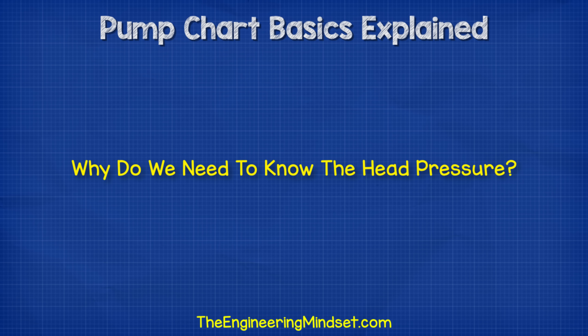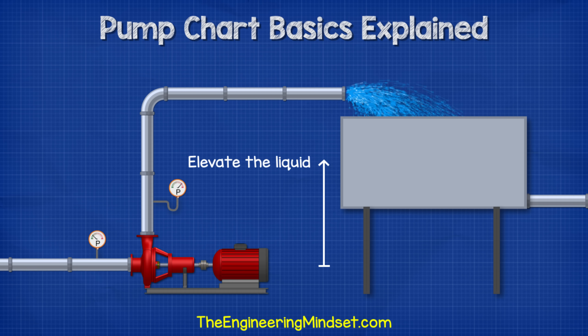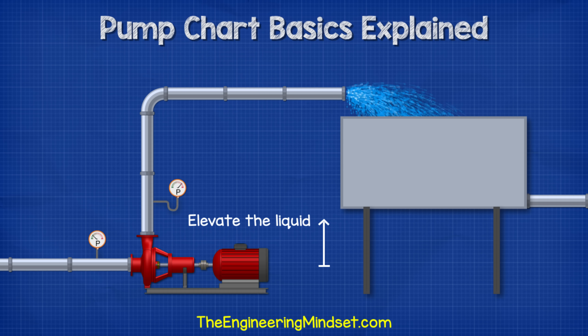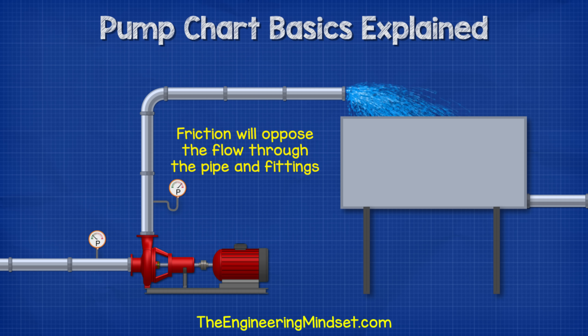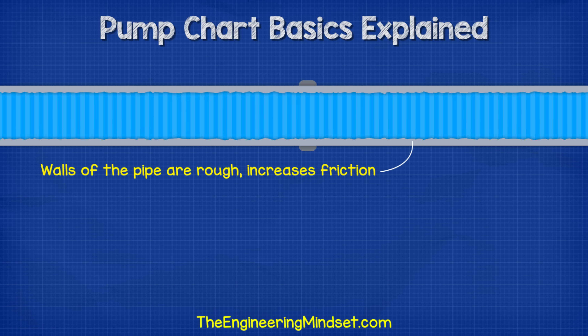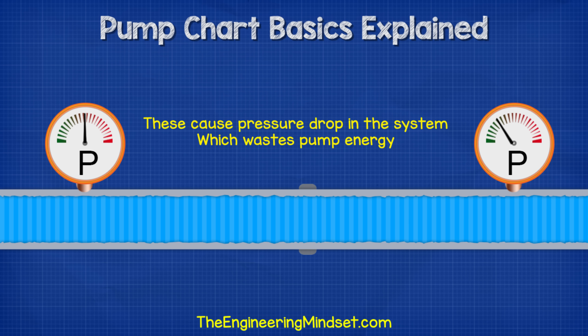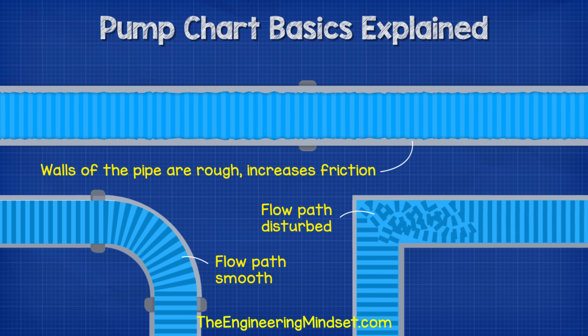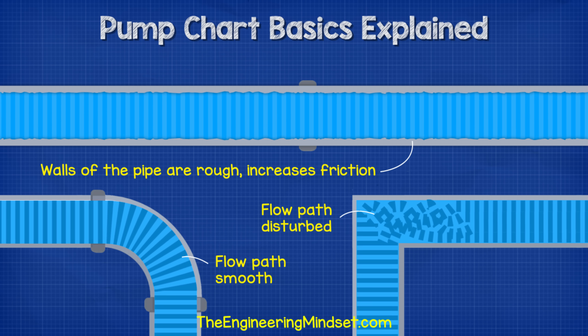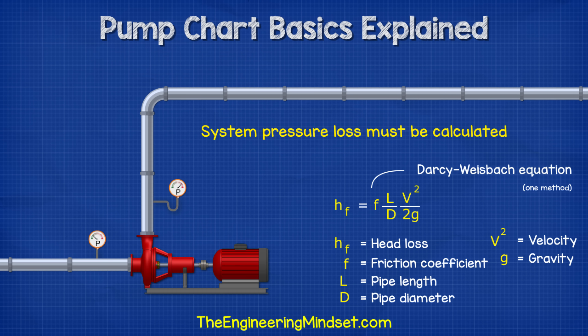Why do we need to know head pressure? Pumps are usually used to move liquid to a higher region, so we need to ensure the pump can reach this elevation. As we pump liquid through the pipes and the fittings, friction will try to oppose the flow. This occurs from the walls of the pipe, but also disturbances to the flow path — this causes pressure losses which wastes energy from the pump. The amount of friction depends on the liquid type as well as the materials and fittings used. Therefore, we must calculate how much friction or pressure loss our system will generate and ensure that the pump we select can overcome this.